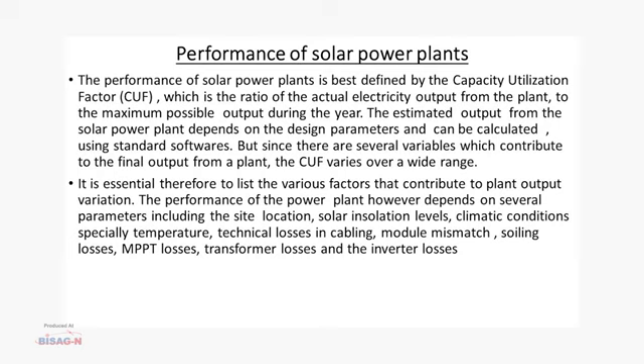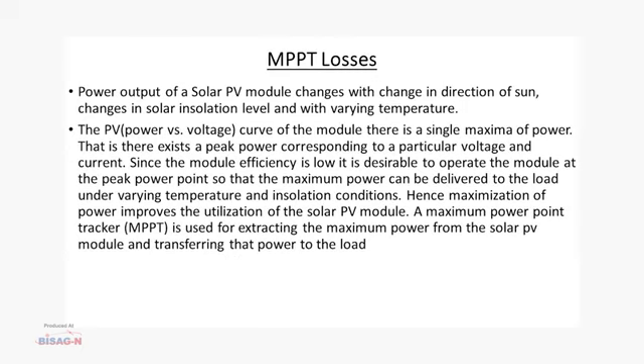It is essential, therefore, to list the various factors that contribute to the plant output variation. The performance of the power plant depends on several parameters, including the site location, solar insolation levels, climatic conditions, especially temperature, technical losses in cabling, module mismatch, soiling losses, MPPT losses, transformer losses and the inverter losses. Let us see what is MPPT losses.